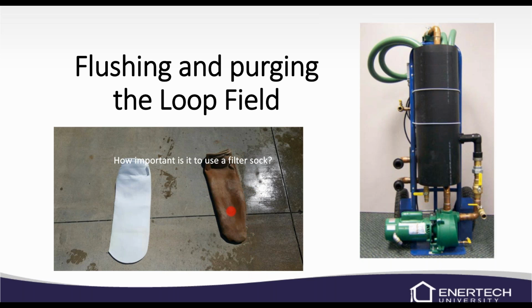This filter sock on the right has been used. You can see it's got a bunch of rust and discoloration. This is a 100 micron bag here, and this is the 1 micron bag on the left, the white one. So we sell these bags. They're washable, reusable. I would definitely use these. They'll collect any kind of debris that got into the piping when the piping was installed. It's better to start out with good quality clean water than it is to go back in there and try to clean it out after you've made a mess of things. So always filter, always flush.